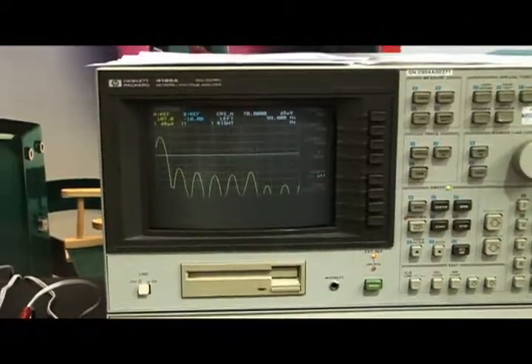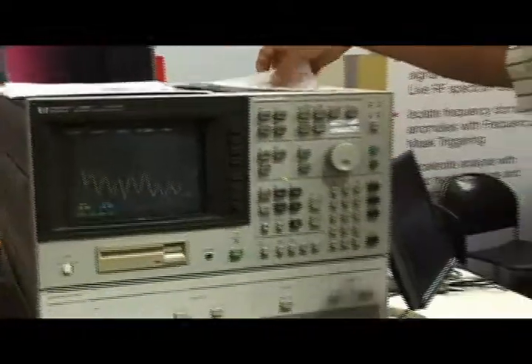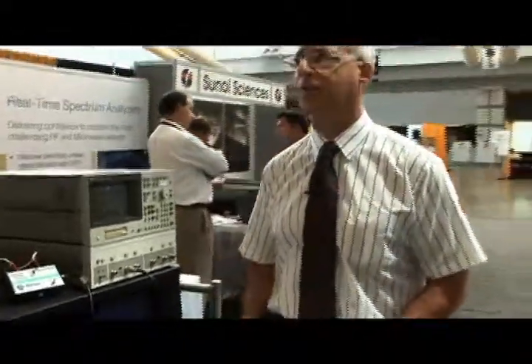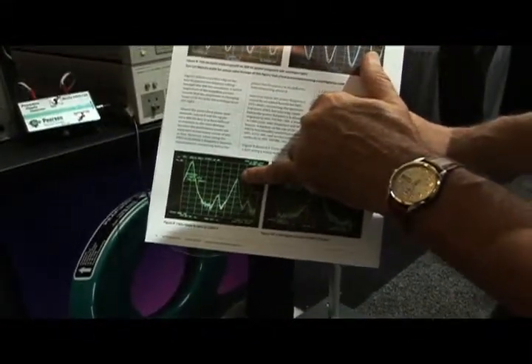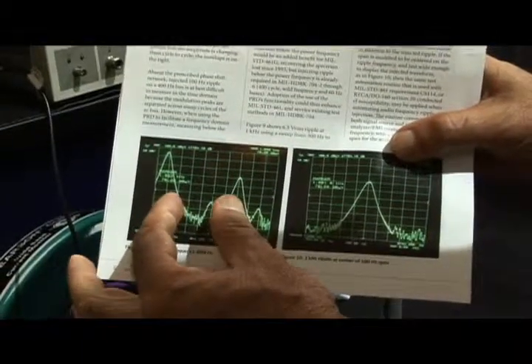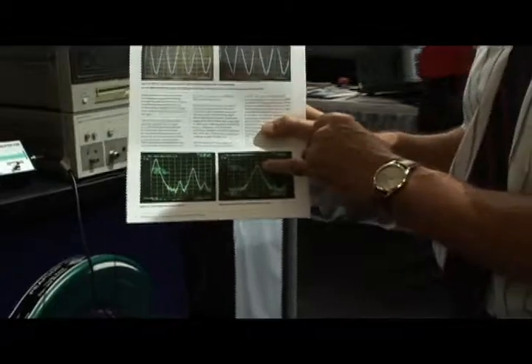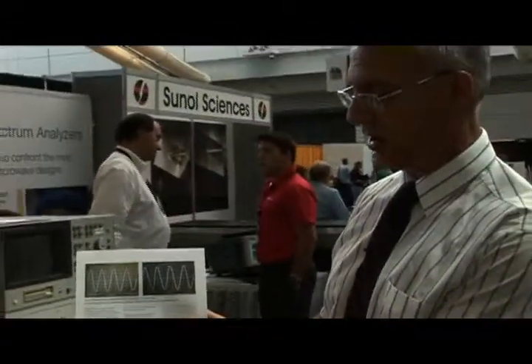Absolutely. Now, this technique makes available a very important function: this test, as it stands, cannot be automated. Everybody likes to automate tests to get them done quicker. With this technique, where we separate the power frequency from the injected frequency, we can put a marker on the injected frequency, command marker to center frequency, squeeze down the span, and you end up with something like this. Once you've got this, you can automate the test — because you can use the same automation as you would with CS114, and just level on that frequency and step to the next. So this device makes automation of this test available.